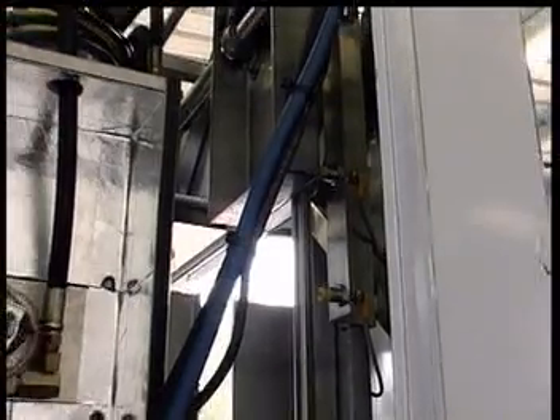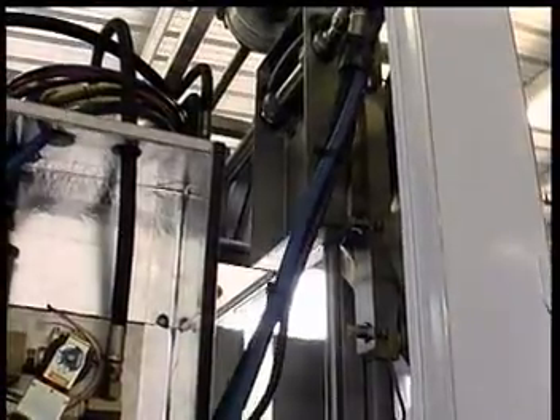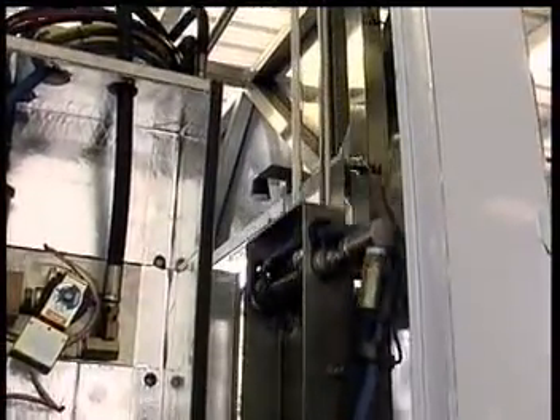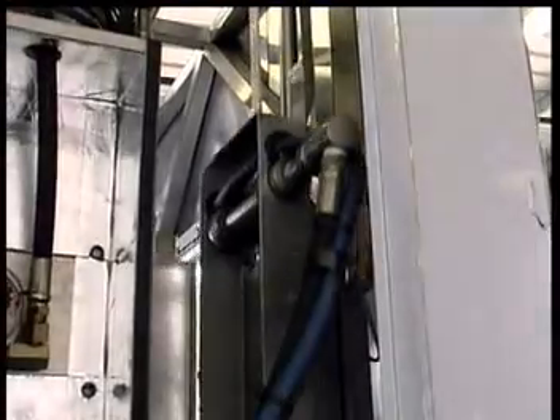It is possible to get this fault with the top prox not being the source of the problem. If the top prox is on and the auto height prox is on at the same time, this fault will be displayed. The auto height prox then needs to be investigated.